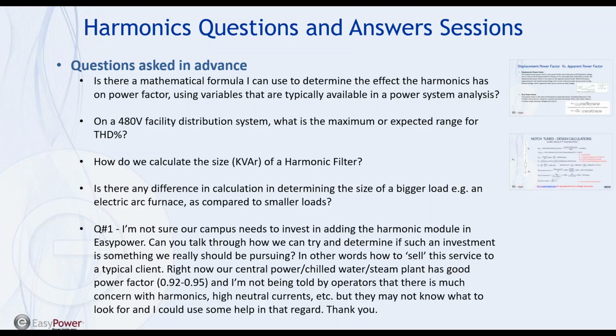I design a harmonic filter system, and I am looking to achieve at least 5% or better voltage distortion throughout the entire plant. If you get to 6 or 7 or 8% voltage distortion down at the 480 volt network, and sometimes it's difficult to get down deep into a network where you might have a large VFD drive pushing distortion up, unless you put a filter at that drive, you may have a difficult time achieving 5% voltage distortion. But this is your target, and you're just trying to design an entire system to have good performance, to not have power quality issues. So using 5% voltage distortion throughout the plant, whether it's the medium voltage network or the low voltage network, is a good number to shoot for. I have seen, however, plants running at 10 and even 12% distortion and not have any types of issues.